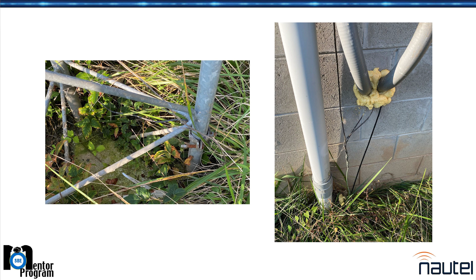That means if you run a lot of current through here, by the time it gets over there you've got X number of ohms of resistance, and you've built up a healthy potential difference between that ground and that ground. That can be a problem, especially if one ground is connected to your antenna or output connector and the other is connected to your AC or ground rod, or in this case, all three.